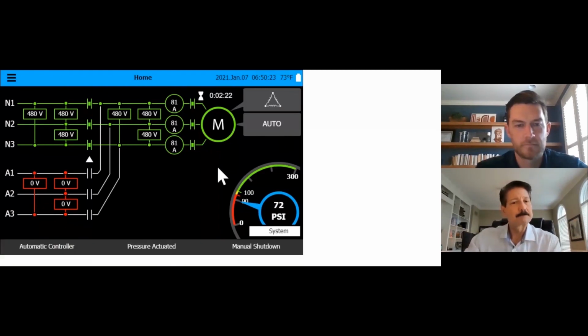So let me bump this back up. As the system pressure increases back up across 100 PSI, which is the cutout, you see the pump on demand's gone, but it continues to run because we have a manual shutdown. And that's required by code, as I mentioned. I'll reiterate that again. If you go automatic shutdown, which is acceptable, and all manufacturers have that, you need the AHJ, whether it's the fire marshal, the local electrical inspector, it could be an FM guy, whoever, they need to sign off on it. It's good to have that in writing. So let me manually turn this off with the button on my demo.